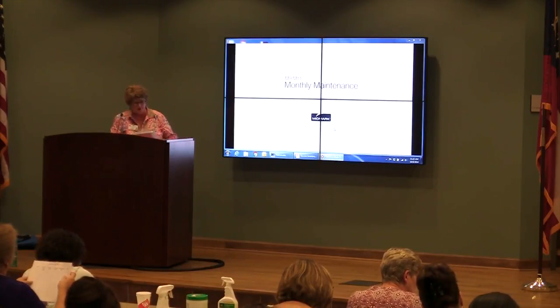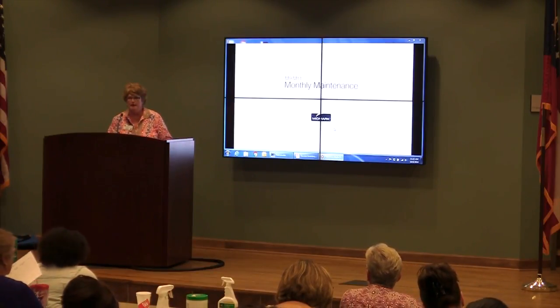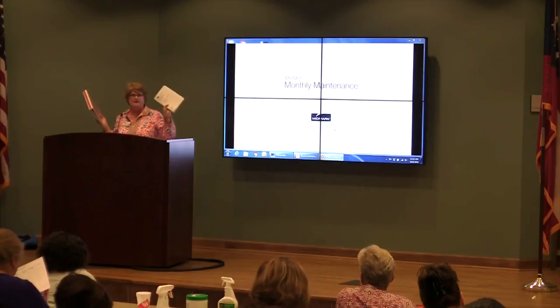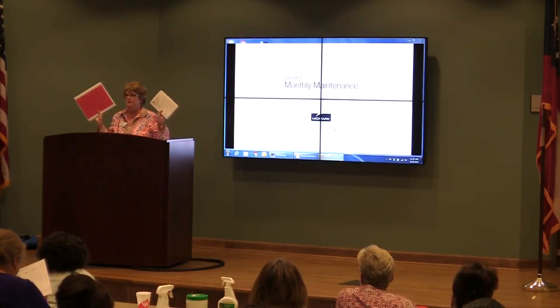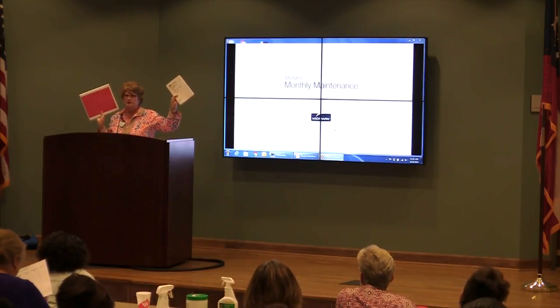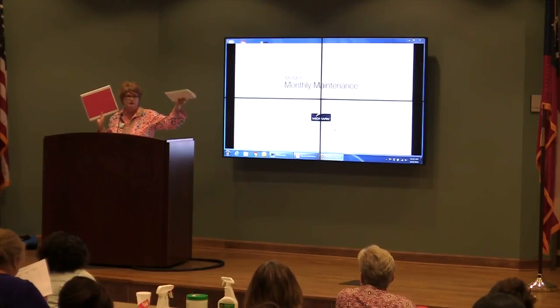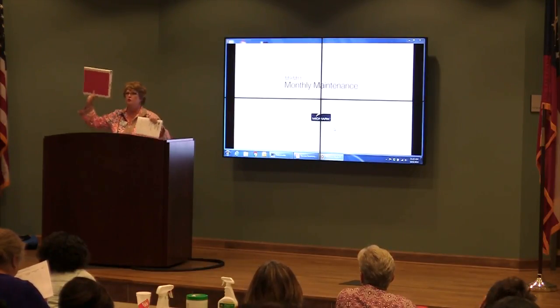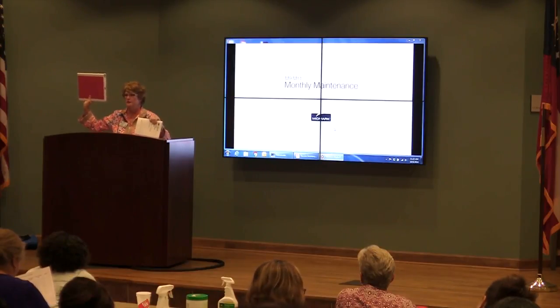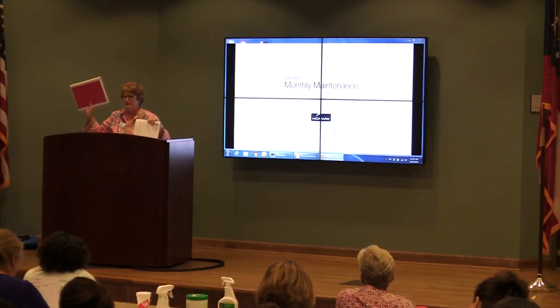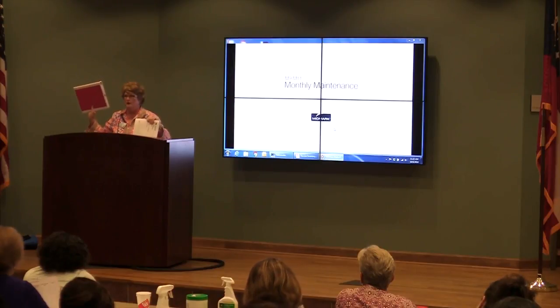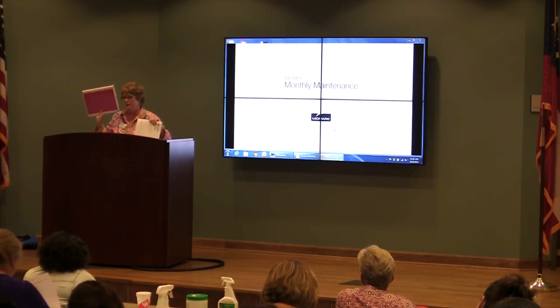There's been some confusion about where you're logging, where you're putting your maintenance, where it is documented. I've gone into clinics and the only book that they're using is the biological indicator book. That's where you're indicating that you're doing your cleaning. That is wrong. You use the red book to document if you've done your cleaning. Everybody should have a red book in their clinic that has a sterilizer. If you don't, let me know. I will get you one. I will bring it to you.